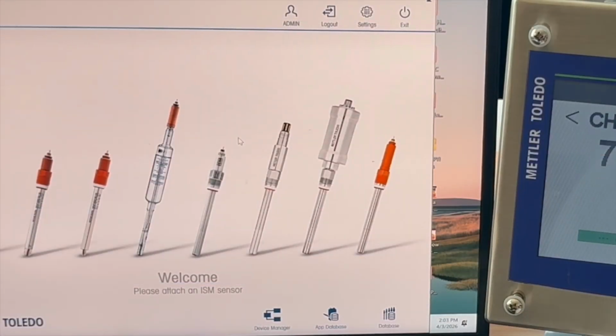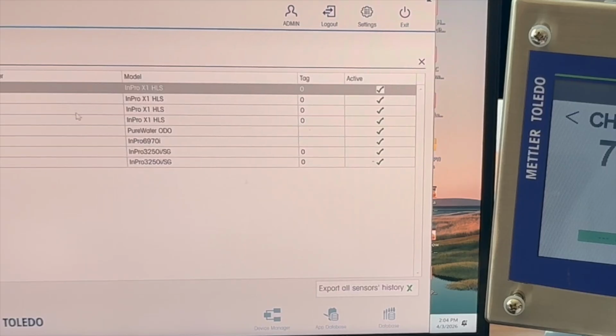Another function of the ISM core software is that it actually acts as a database. So here's how you can actually track and manage the assets that are used at a specific plant. If you've got like 2 pH sensors in your facility, this isn't that big of a deal. But when you're in a refinery or other facilities where you've got 10 to 100 or more sensors, having a database is a way to actually manage these assets. I don't have to have a sensor attached. I go down here to where it says database, and any sensor and all sensors that are connected to this will be registered. So these are just sensors that have been attached over time.